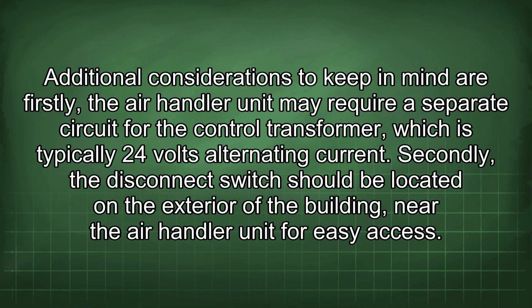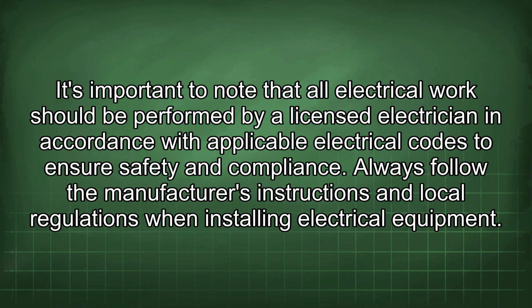Additional considerations to keep in mind are: firstly, the air handler unit may require a separate circuit for the control transformer, which is typically 24 volts alternating current. Secondly, the disconnect switch should be located on the exterior of the building, near the air handler unit for easy access. It's important to note that all electrical work should be performed by a licensed electrician in accordance with applicable electrical codes to ensure safety and compliance. Always follow the manufacturer's instructions and local regulations when installing electrical equipment.